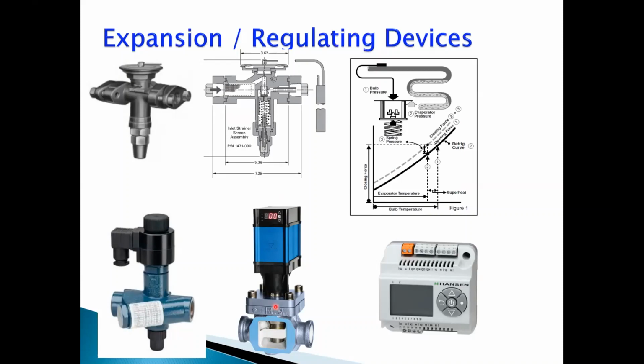As low as 2 degrees superheat can be maintained using an electronic expansion valve. That saves a lot of energy. Earlier, the thermostatic expansion valve used to operate at around 5 to 8 degrees superheat. Now that has been brought down to 2 degrees centigrade. That's a huge energy saving. Of course, the only limitation right now is that the cost of these expansion valves is very high.